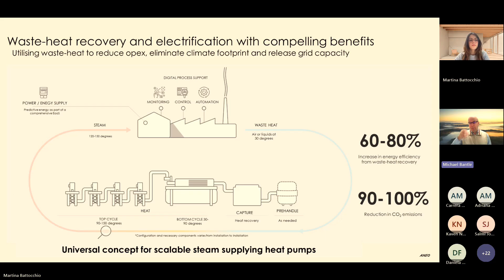Yeah, this is basically what Martina introduced. The heat pump system which we have installed there is producing 2 tons of process steam per hour, also some hot water. That gives us a capacity, depending on demand, of 1.4 to 1.8 megawatt, which is the capacity that this heat pump can supply. And as I said, it recycles the waste heat from a drying process. I'll come back to that a little bit later. It's running at a COP of 3.0 for a temperature lift of close to 100 Kelvin. I guess this is quite a good COP, and maybe also the reason why we got this award from EHPA.